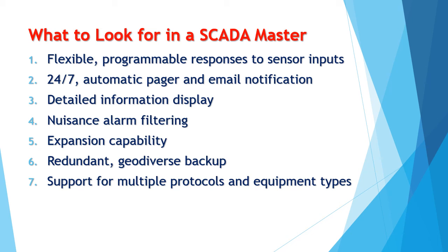Fourth, nuisance alarm filtering. Nuisance alarms desensitize staff to alarm reports, and they start to believe that all alarms are non-essential alarms. Eventually, they stop responding even to critical alarms. Look for a SCADA Master that includes tools to filter out nuisance alarms. Next, expansion capability. A SCADA system is a long-term investment that will last for as long as 10 to 15 years. So you have to make sure it will support future growth up to 15 years.